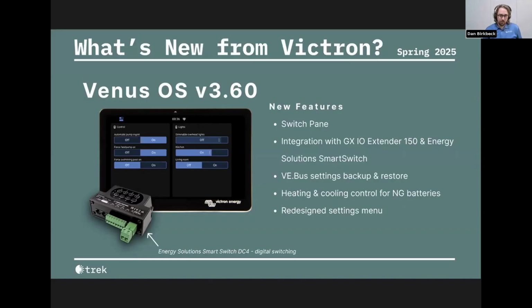In addition, they've added VE bus configuration settings backup and restore for inverter charger settings. So now when you do a firmware update, you don't have to reprogram the whole inverter charger again. Anyone familiar with doing a firmware update for these inverter chargers knows it'll wipe those settings, but not anymore if you've got a GX device running this Venus OS 3.60.